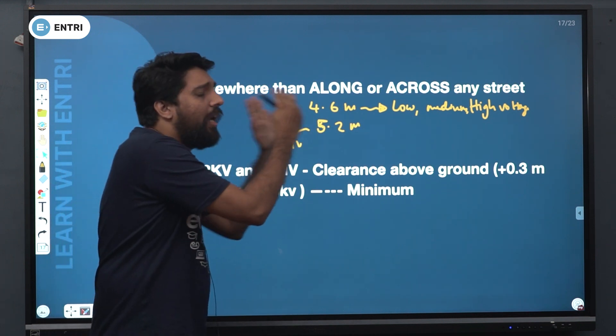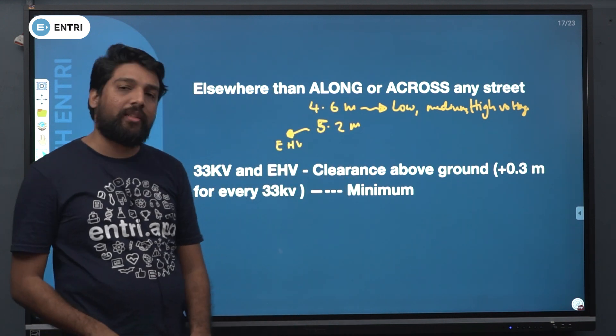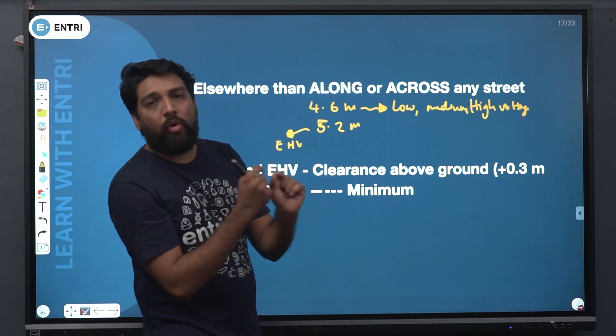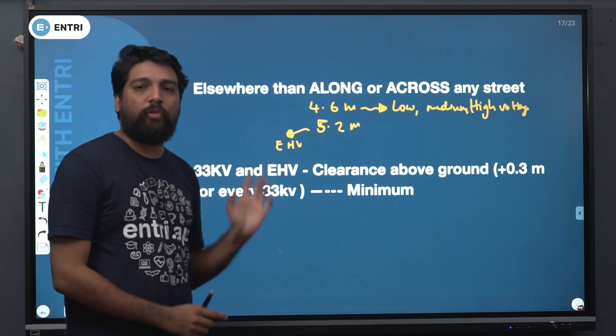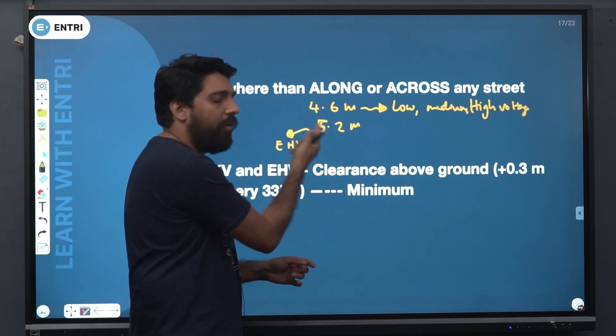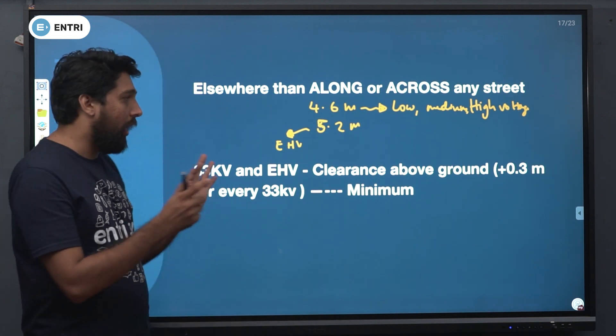Elsewhere than along or across any street: if it is having low voltage, medium voltage, or high voltage, your answer is 4.6 meters. If you are having extra high voltage, your answer will be 5.2 meters.